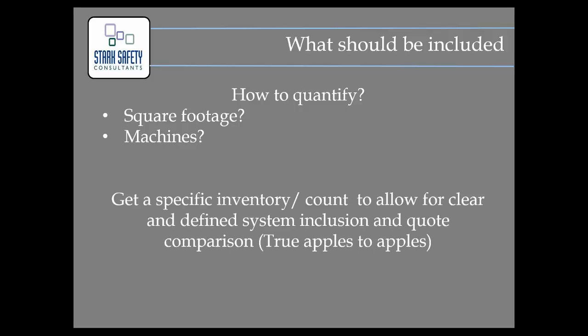Our recommendation, the best option, is to get a specific inventory and count. We actually just got an RFP sent to us this morning where they did their own count on their system. They didn't use parameters based on IEEE 1584 or based on 480 and above — they literally did an equipment count, with specific numbers of disconnects, panels, transformers, etc., and that's what they wanted the quote based on.